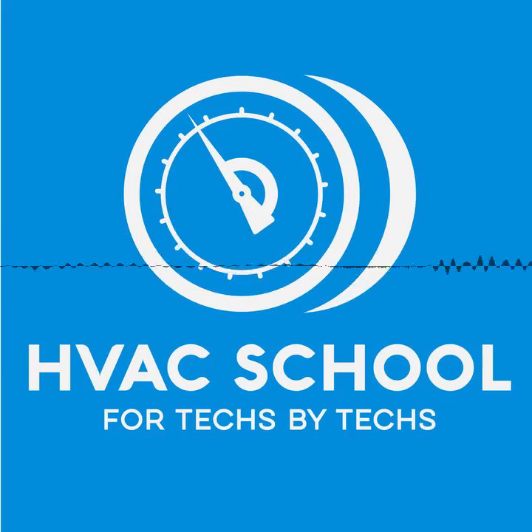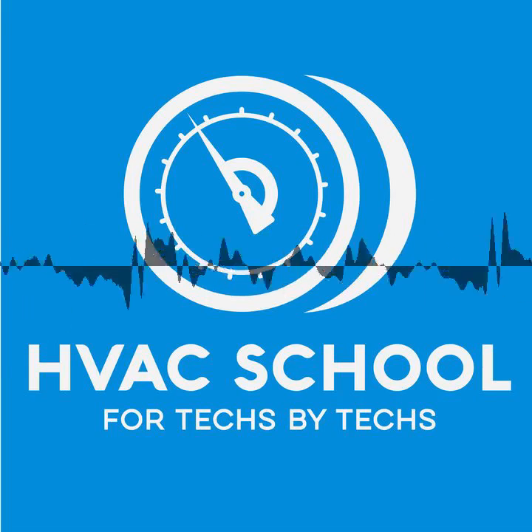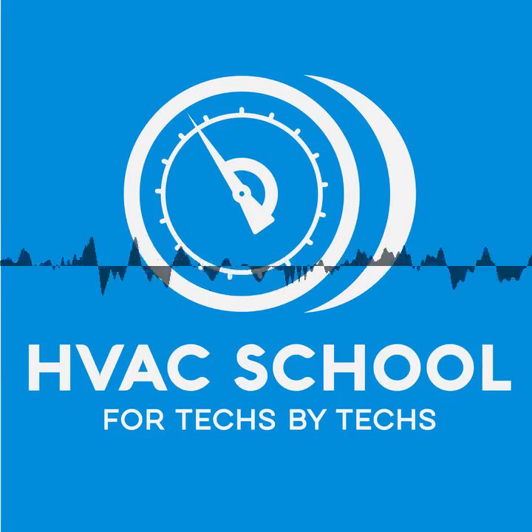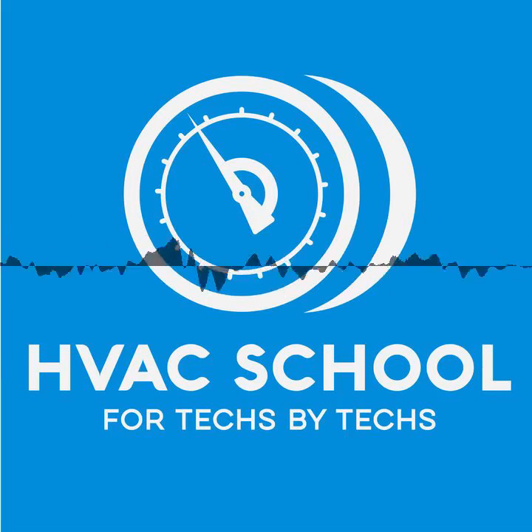And so you can pretty much, if you're calculating system capacity, count on 800 CFM. I got you. As long as you're in that range. I got you. And so even though your measurement's not going to be nearly as accurate, and you haven't fixed the inaccuracy with the measurement, it becomes less important if you're reading 0.5. And so you can go ahead and say, all right, I can be pretty confident that I'm at 800 CFM, or at least thereabouts. Yeah, I misunderstood what you were saying. No, you're correct right there. Yep, that's a correct statement.